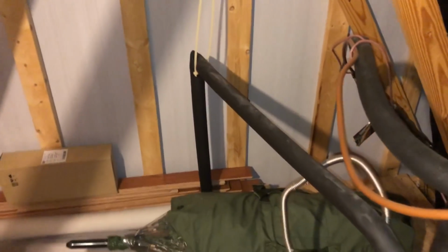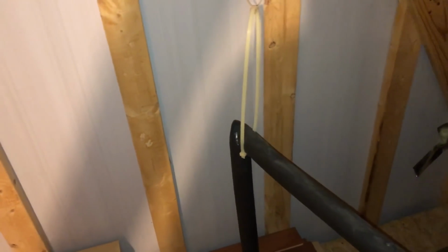All right, so that 1-inch pipe down there pretty much has to be it. There goes our pan that way, and here goes our primary this way. So I'm guessing that somewhere they have switched from 3/4 to 1 inch in the wall, I guess. First I thought they had upgraded from a tank type water heater to the tankless, and then I saw them everywhere in here. So I guess that 1 inch out there is actually this. So I'm going to find out a couple of different ways.